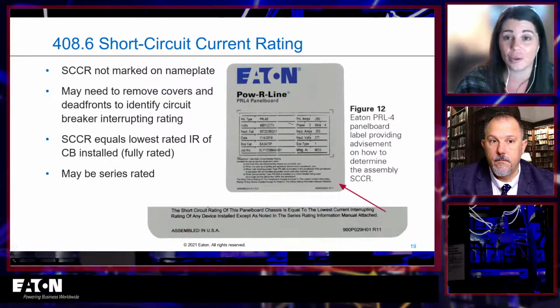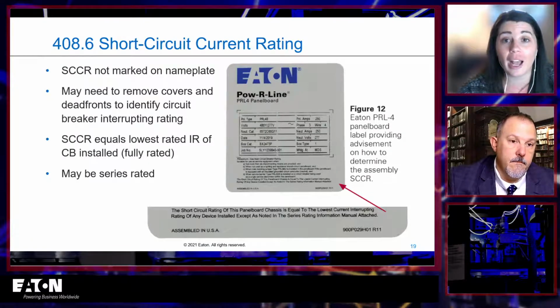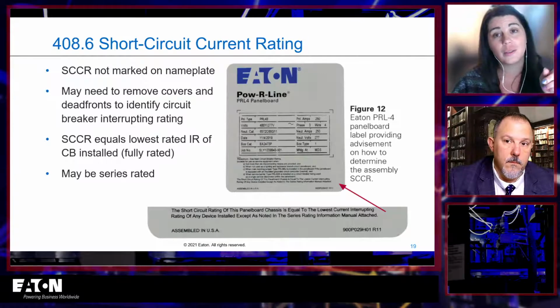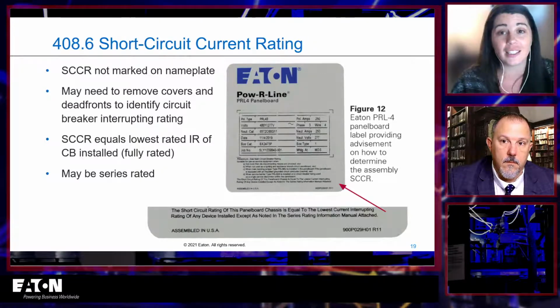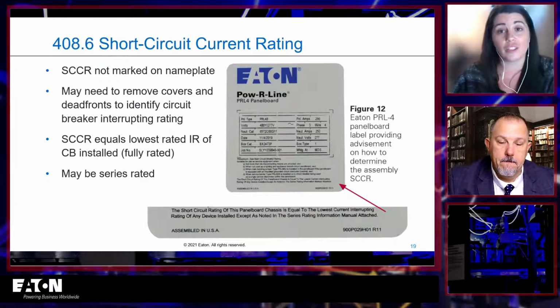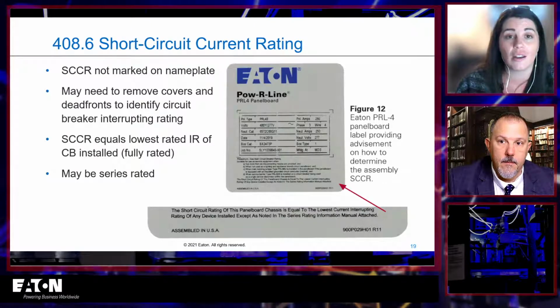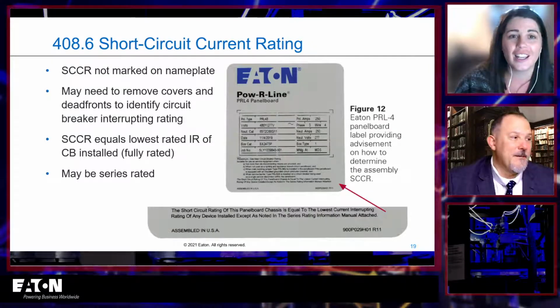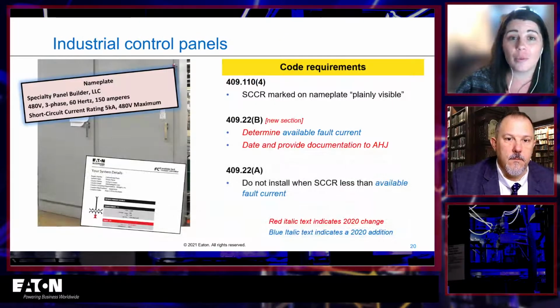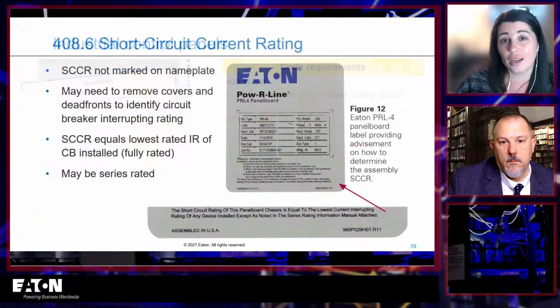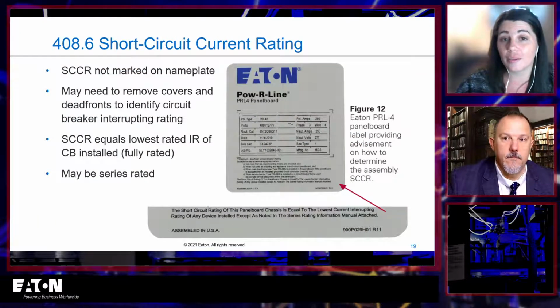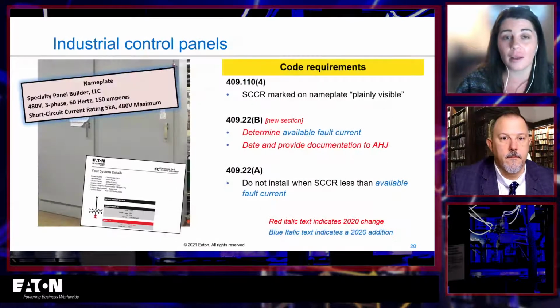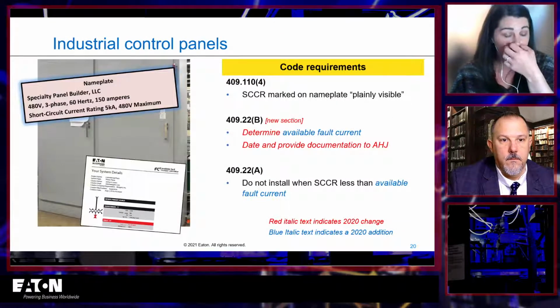Right. I agree that precisely it's a recipe. So you do have to be able to figure out what that is. I would love for it to get a requirement the way that transfer switches do for SCCR. We'll go into what transfer switches get, but it's just a little teaser for when we get to transfer switches. There you go. And then panel boards can also be tricky because they can be series rated. We'll go into series ratings later, provided that we still have time. But it can get really complicated with the ratings for those.